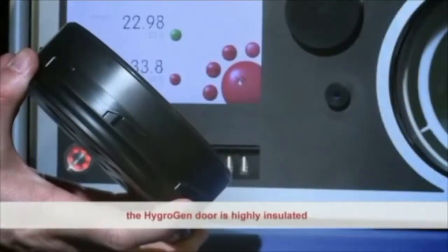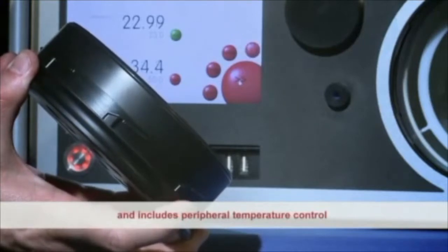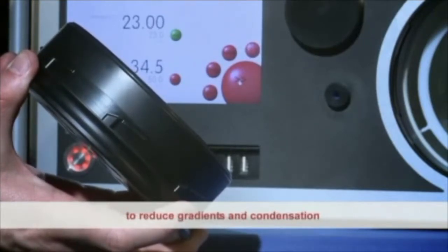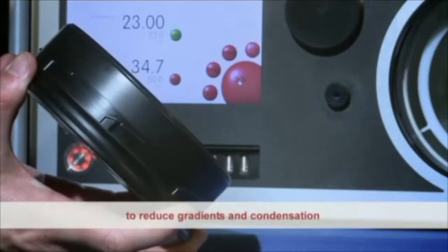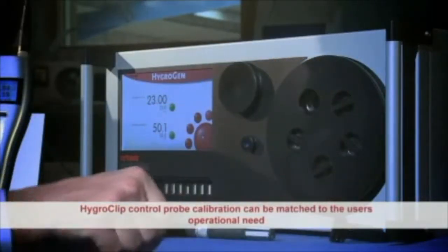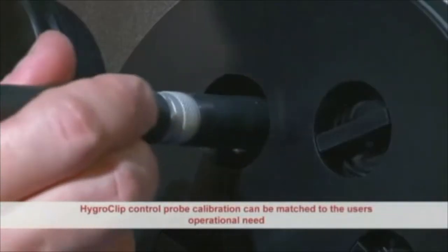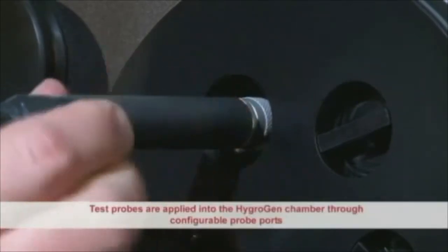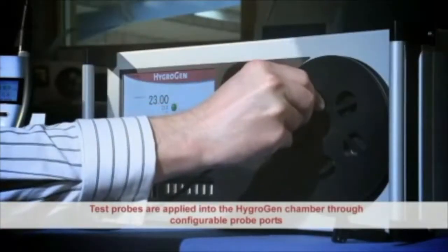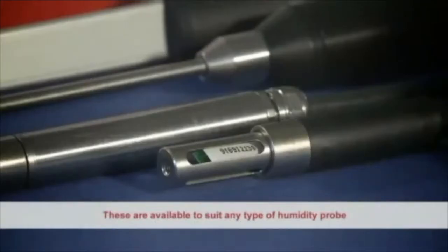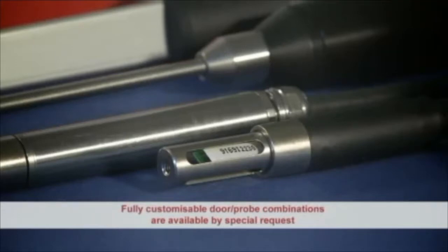To achieve temperature stability and gradient specifications, the HygroGen door is highly insulated and includes peripheral temperature control to reduce temperature gradients and condensation when running at high temperature conditions. The HygroClip control probe can be calibrated exactly to match the user's operational need. Test probes are applied into the HygroGen chamber through configurable probe ports. These are available to suit any type of humidity probe. Fully customizable door probe combinations are available on special request.